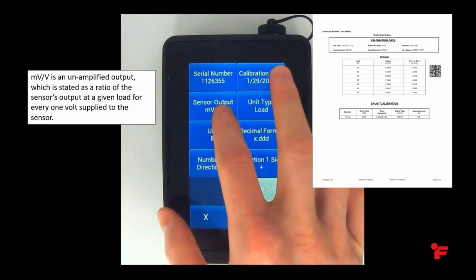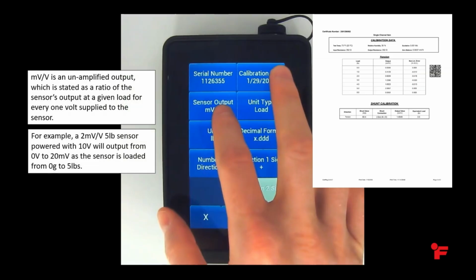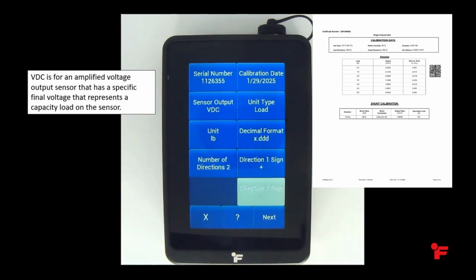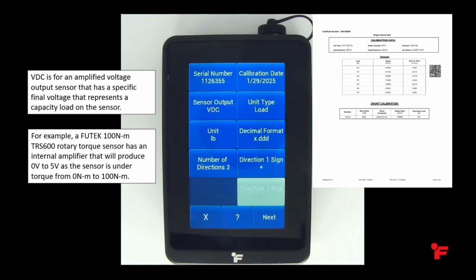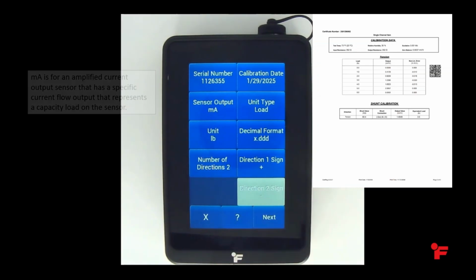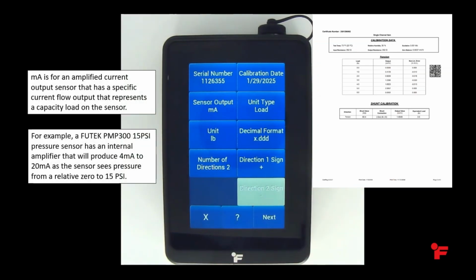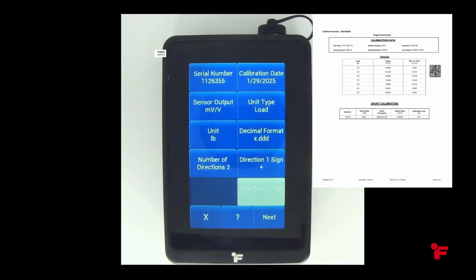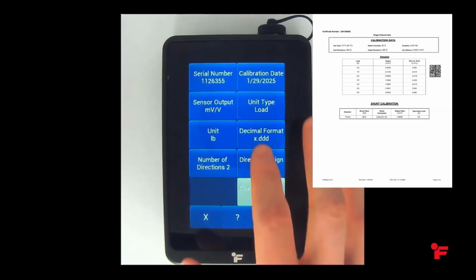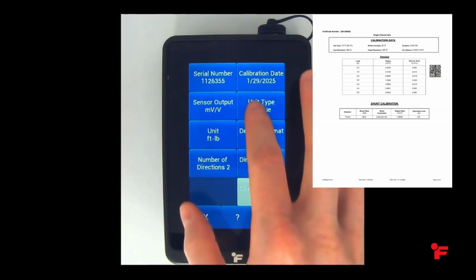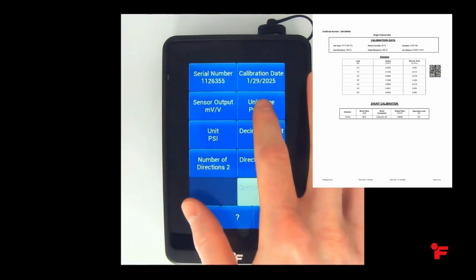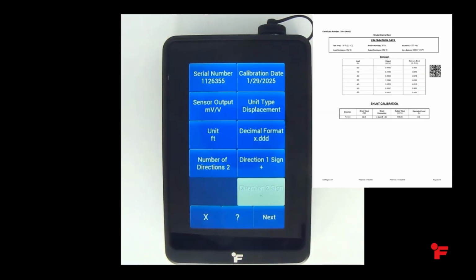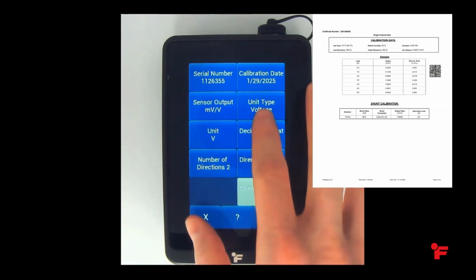Sensor output specifies the output of the sensor that will be connected to the SENSLOG instrument. It will be millivolt per volt for unamplified, VDC for amplified voltage, and mA for amplified current. The calibration shows the results read from the sensor were in millivolts per volt, so we will select millivolt per volt on the SENSLOG. The unit type will determine which units will be available for our readings. The calibration certificate lists the loads and capacity of the sensor in pounds, so we will set our units as pounds.